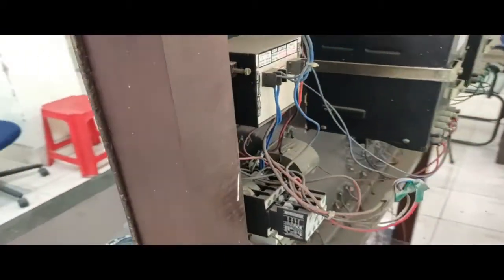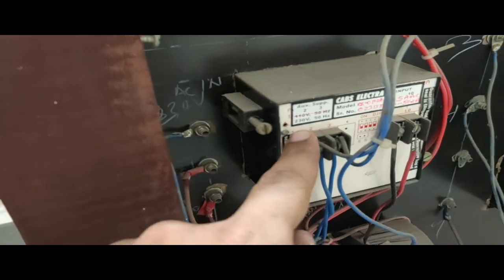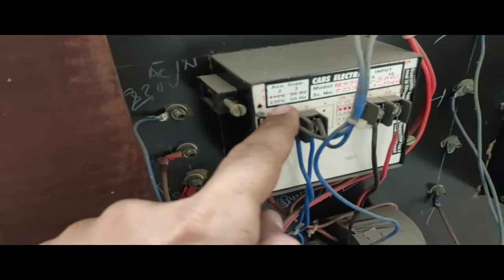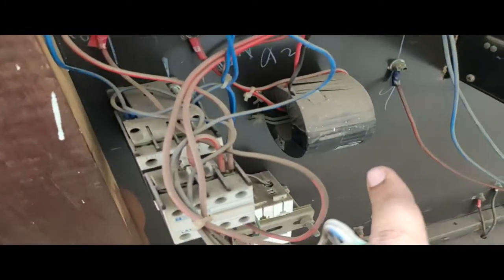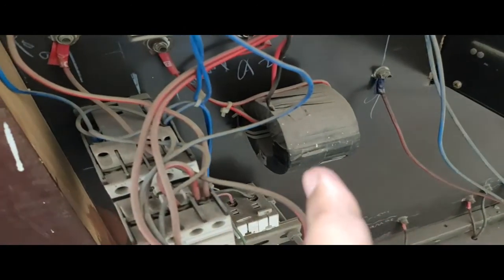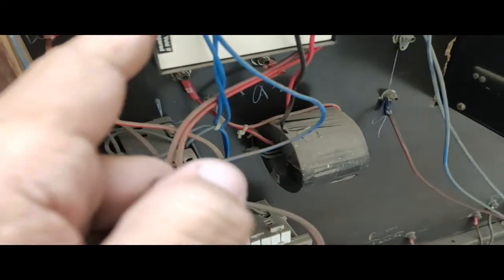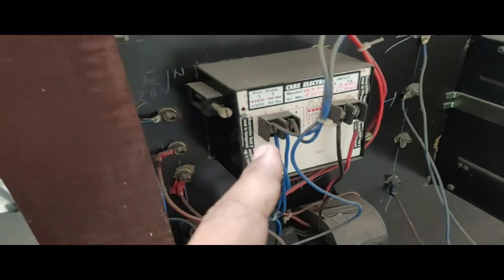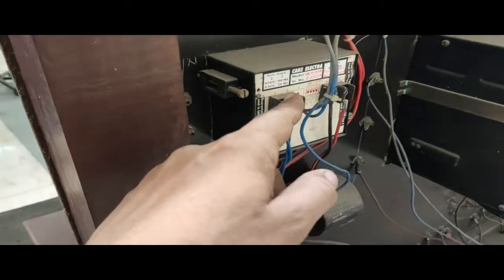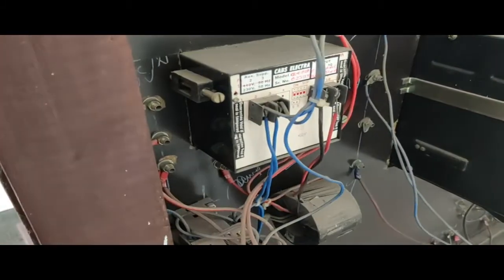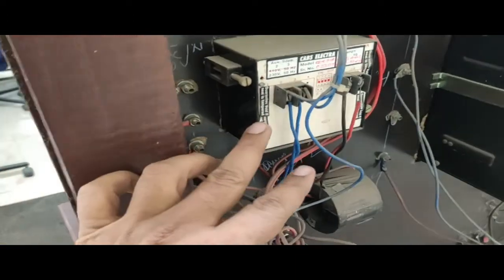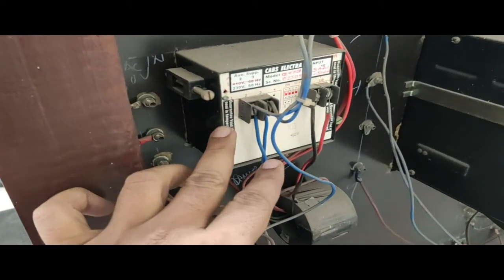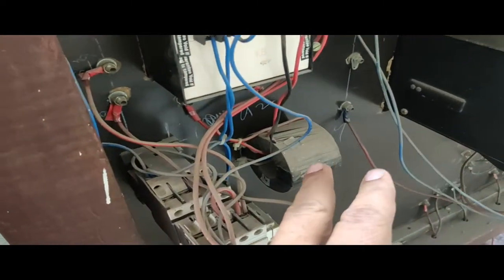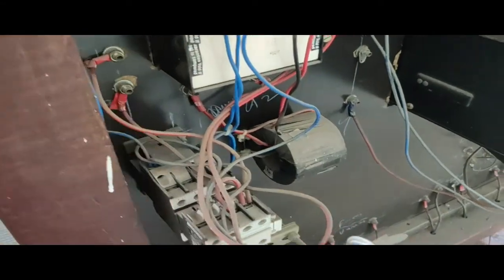Now coming to the back side of the panel. Here you see, as I mentioned, this is the digital ammeter. One CT is required. In the CT primary the main current will flow, and in the CT secondary, with some conversion ratio, it will be converted into a digital value and reflected on the display panel. As the digital circuit works on a very low amount of current, the CT is required for converting the current.